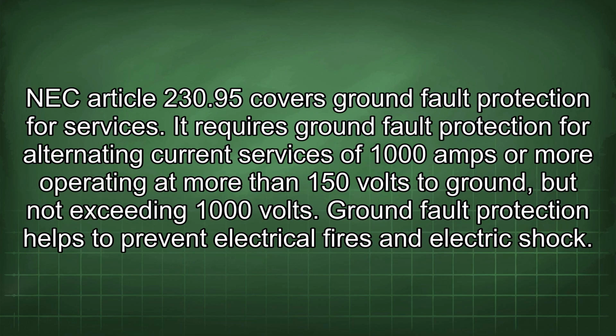NEC Article 230.95 covers ground fault protection for services. It requires ground fault protection for alternating current services of 1000 amps or more operating at more than 150 volts to ground, but not exceeding 1000 volts. Ground fault protection helps to prevent electrical fires and electric shock.